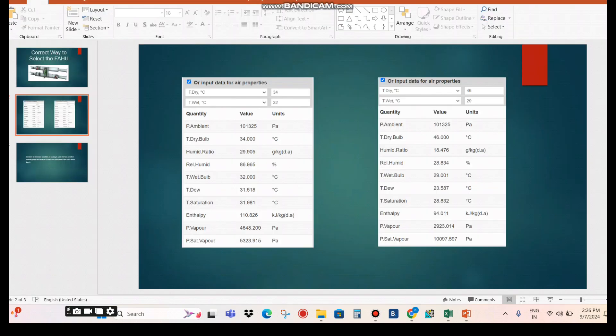When it comes to FAHU selection, the outside air enters the cooling coil and gets cooled. The dry bulb and wet bulb temperatures as per Dubai Green Building Regulation for air conditioning design are 46°C dry bulb and 29°C wet bulb. The corresponding relative humidity for these conditions is normally around 28.8%. However, when selecting the FAHU cooling coil, temperature and relative humidity alone are not sufficient — the third critical parameter is absolute humidity, also called the humidity ratio.